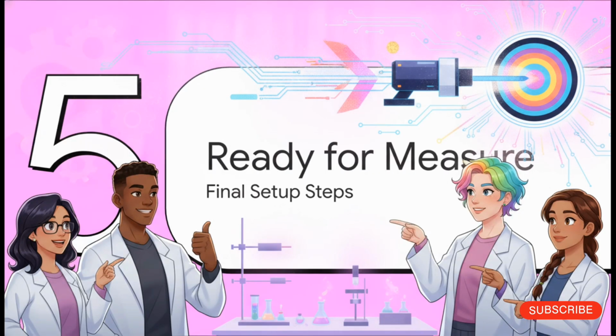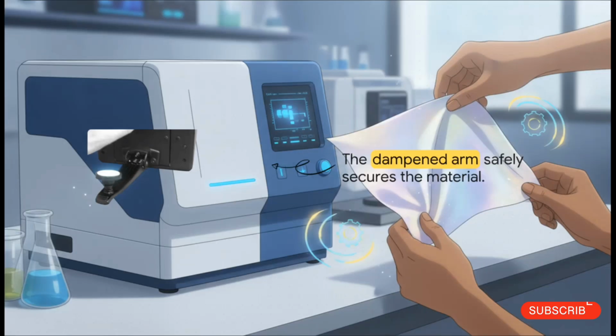Finally, Section 5. We are ready for measurement. Just a few final setup steps to go. So for standard reflectance measurements, you'll be using the sample arm right at the front of the unit. And if you're handling delicate materials and you're worried about crushing them, seriously, don't be. You just grasp the arm, pull it fully open towards you, present your sample at the viewport, and let go. The spring on this sample arm is mechanically dampened, so it closes smoothly, slowly, applying exactly the right amount of pressure to safely secure the material without causing any damage whatsoever.